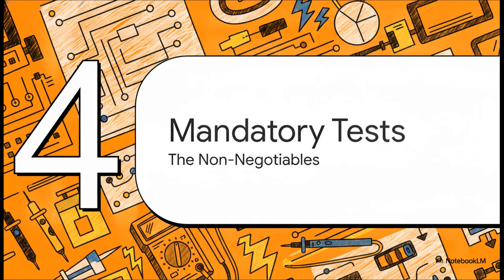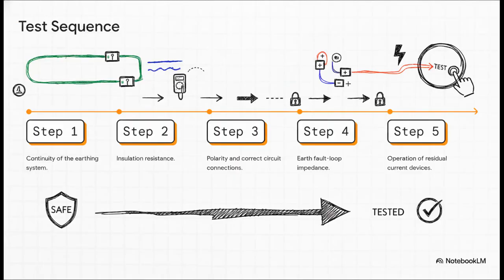Part 4. Mandatory electrical tests. These are the absolute non-negotiables. Now pay close attention to this strict chronological dependency. You cannot just do these tests in whatever order you feel like. It is a highly specific logical sequence. Step 1 is always the continuity of the earthing system.